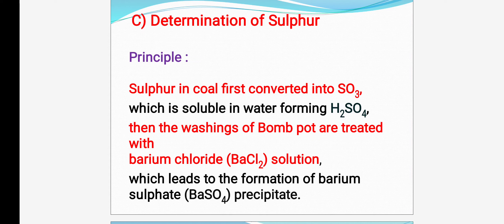Coal contains sulfur. Sulfur in coal is first converted into sulfur trioxide. As you know, burning of coal takes place in the presence of oxygen, so sulfur reacts with oxygen and produces sulfur trioxide. The produced sulfur trioxide then dissolves in water. There is 10 ml of distilled water in the bomb pot, placed especially for dissolving the produced gases. After dissolution, it produces H2SO4 inside the bomb pot.